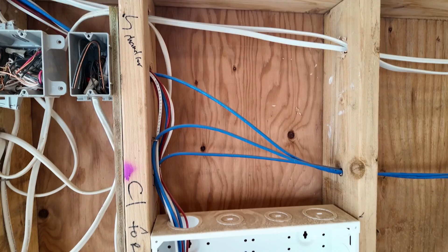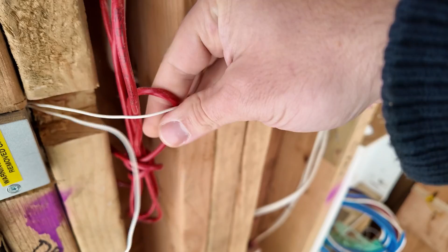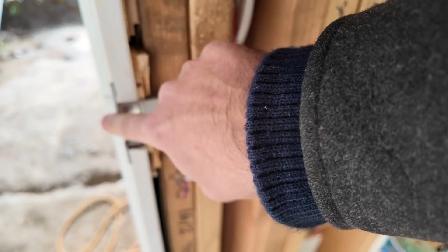This is the actual latch for the door, now installed in the door frame. This is the electronic latch, 12 volts. I still need to connect these wires before we close this up, which is happening right after I film this. This separate wire runs into the low voltage box for powering this relay. So when the door controller wants to unlock the door, it just applies 12 volts to that, which releases it, and then this can flip.